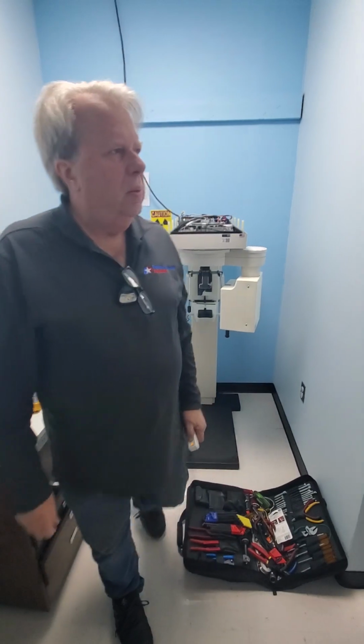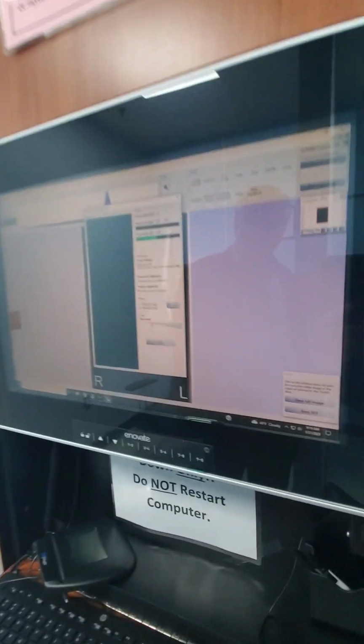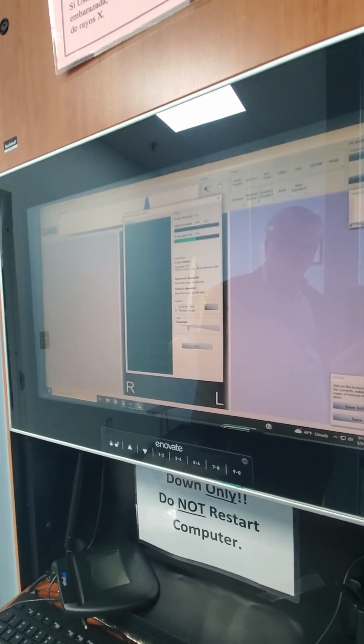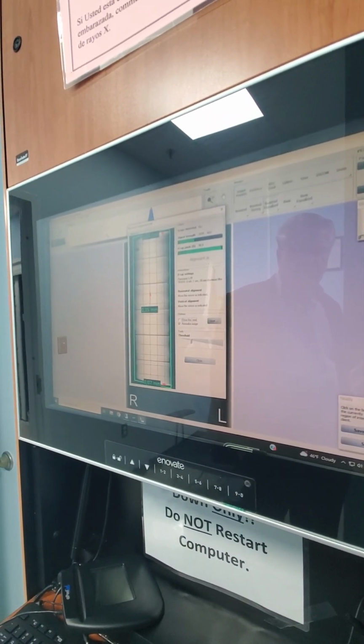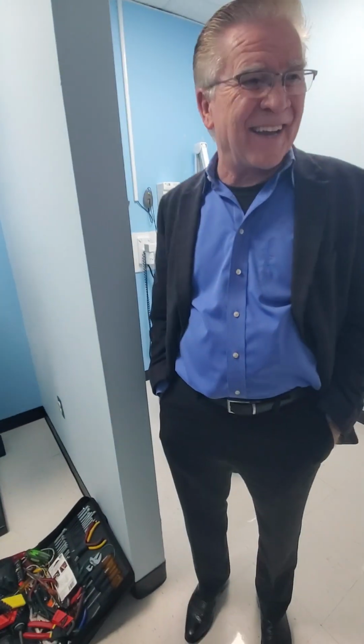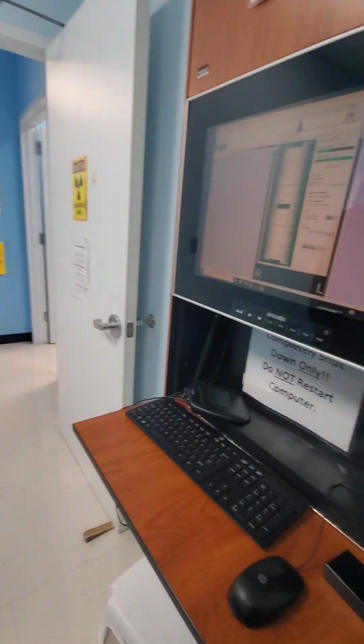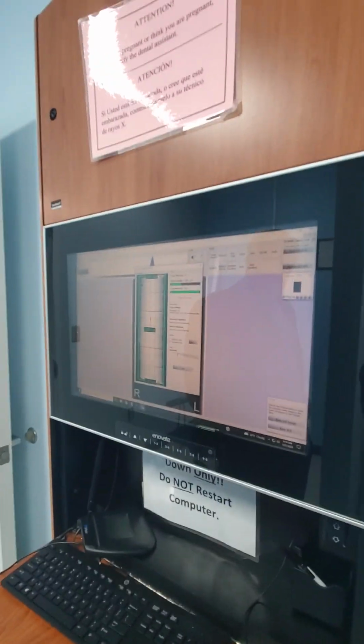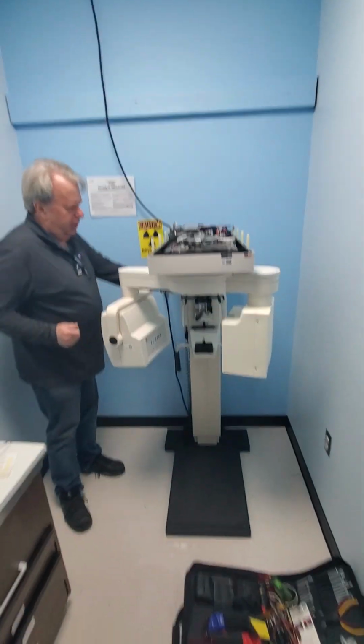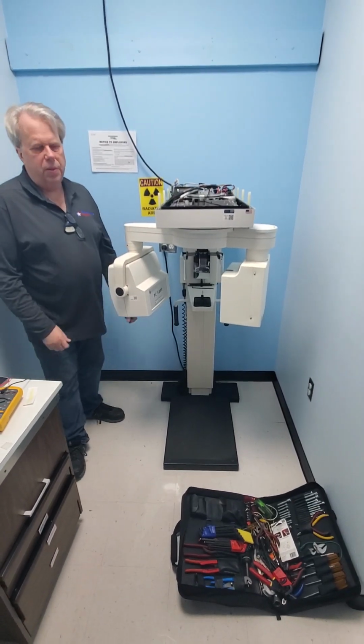Is that a software adjustment or a mechanical adjustment? Mechanical. So that's dead on. That's dead nuts right there. That's beautiful. It gets no better. Alright, so we're aligned. That means nobody's bumped the tube head to move it out of alignment or anything like that.